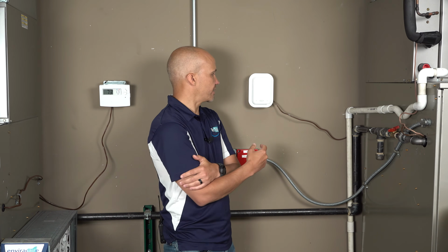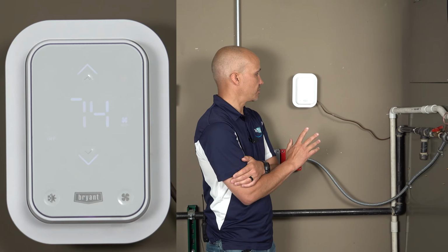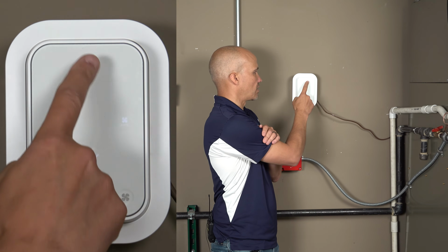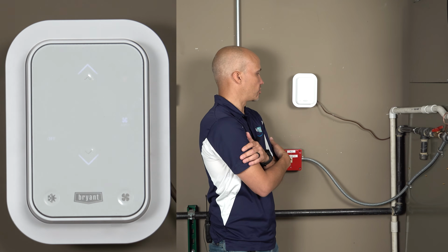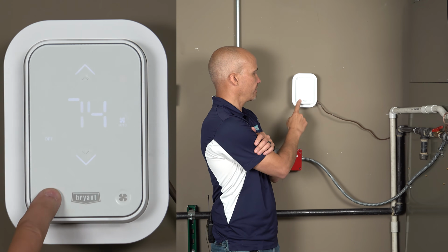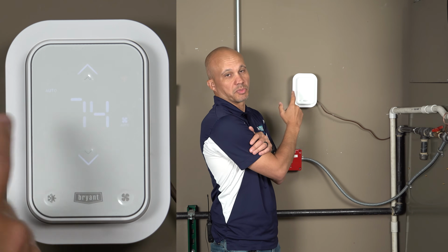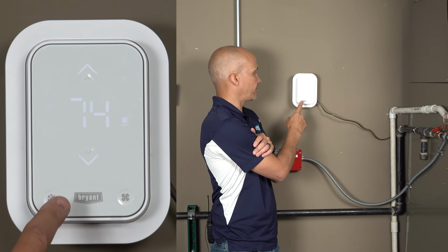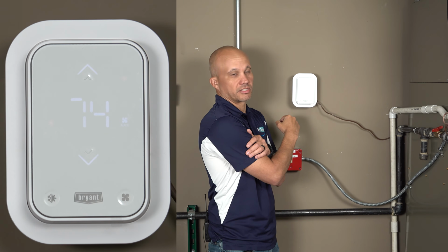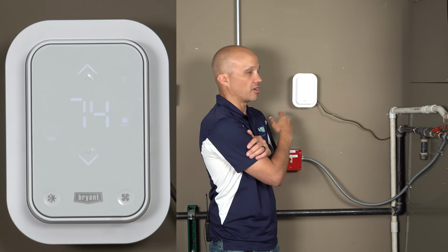All right, a quick little navigation. There's only 4 buttons on this thermostat. There's the up and down arrow, which are pretty self-explanatory. Those will obviously change the set point that you're trying to control to. There's a mode button on the left-hand side over here. Right now it says off. If I toggle that, it goes to auto, which means it can run heating and cooling. If I toggle it again, it gives me the little cooling snowflake. Again, gives me the little red sunshine for heating, and then back to the off mode.